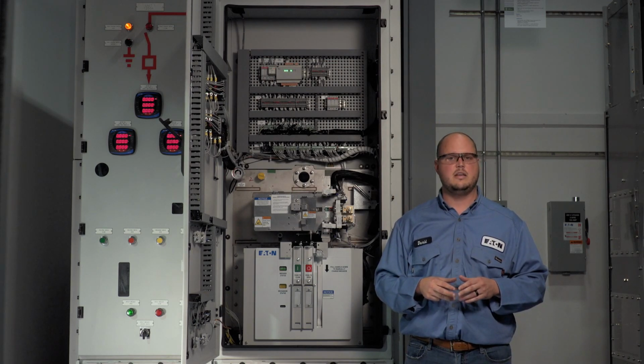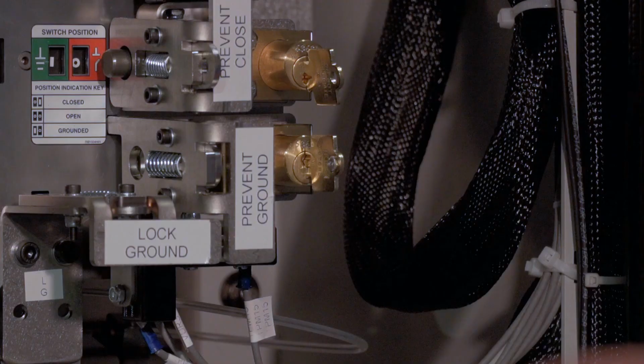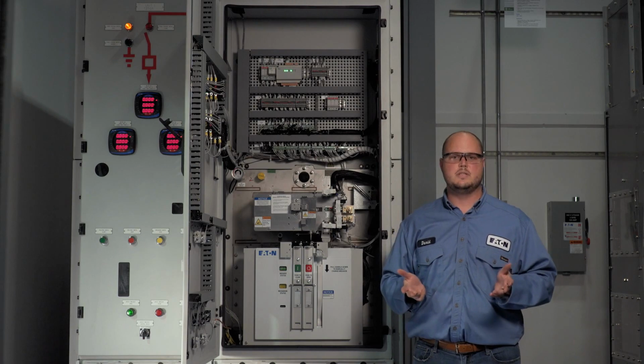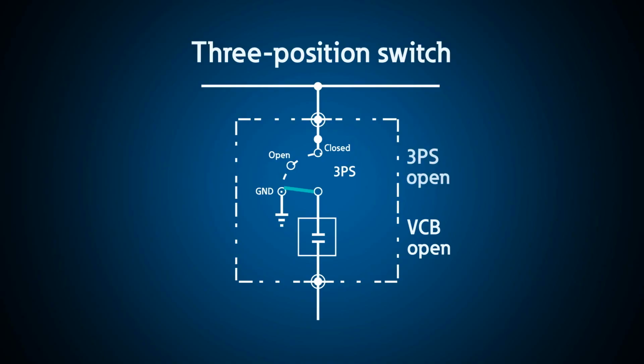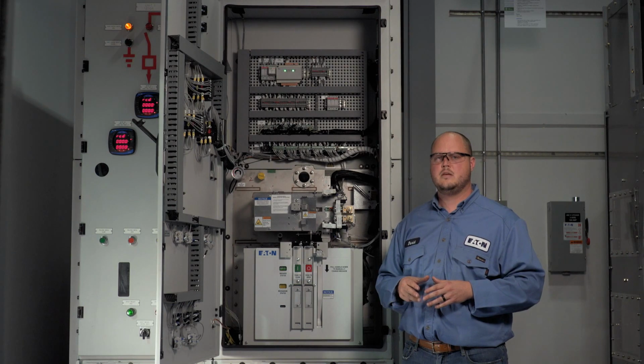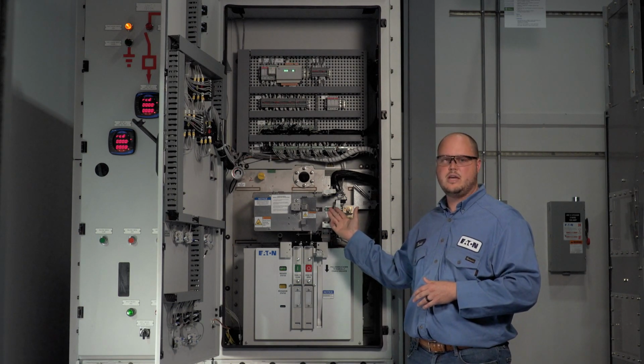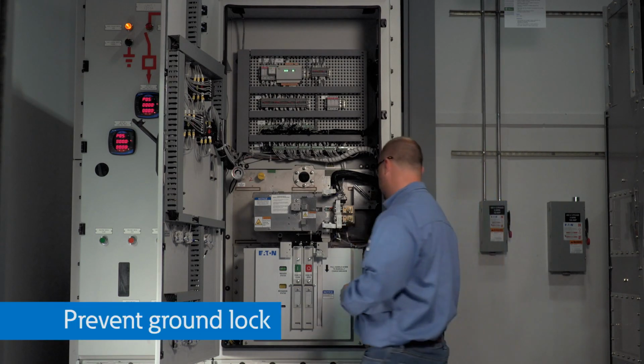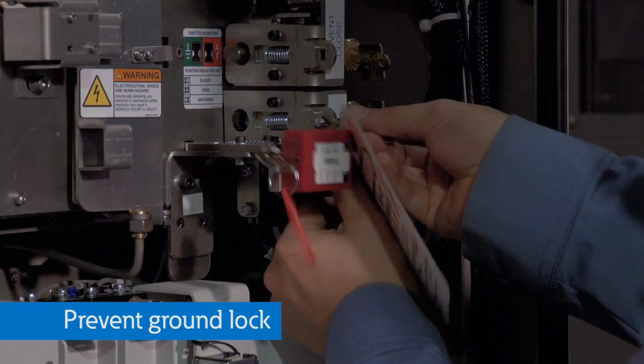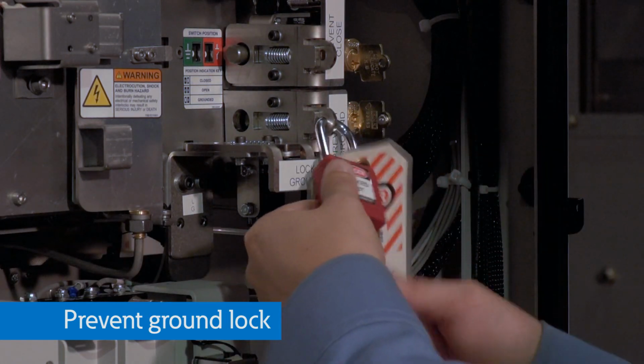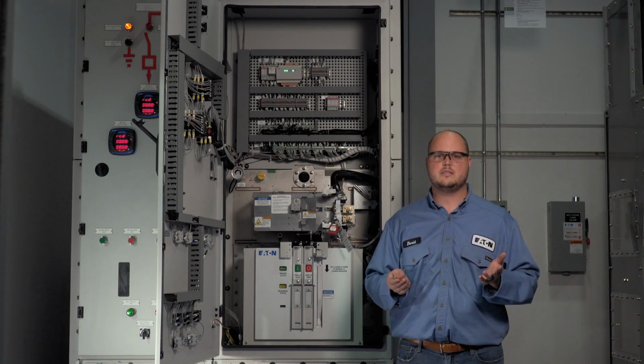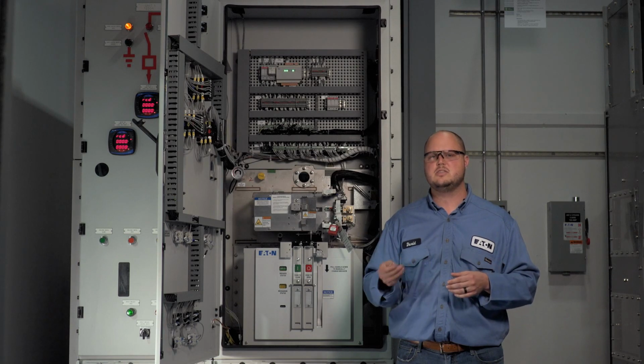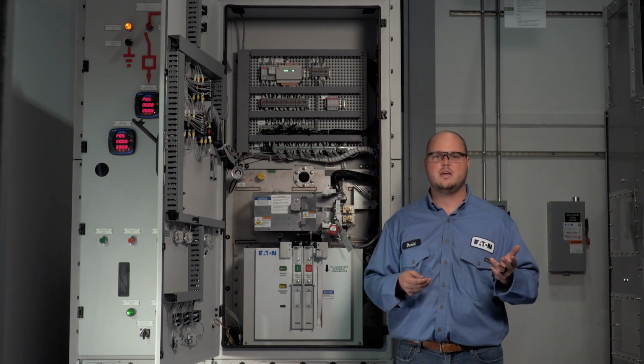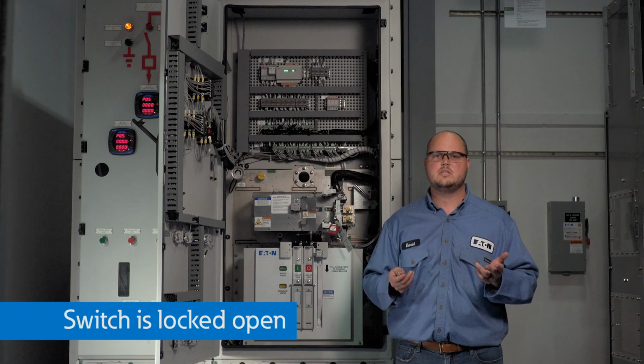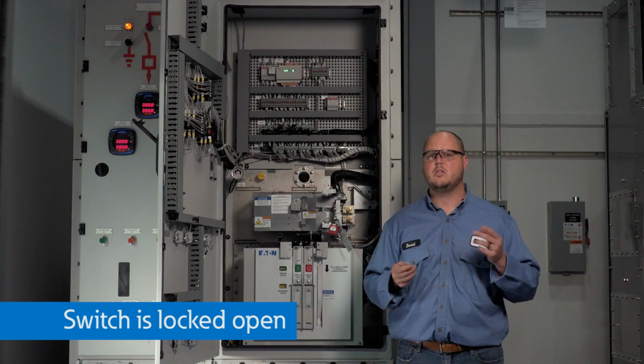Notice that the prevent ground lock cannot be engaged while the switch is in the grounded position. I will return the switch to the open position. Now that the switch is in the open position, I will engage the prevent ground interlocks and apply a padlock. Again, all 4 of these switch interlocks have provisions for hasps or padlocks to be used in addition to the key lock system. With both the prevent close and prevent ground interlocks engaged, the 3-position switch is confined to the open position. The switch cannot be closed or grounded.